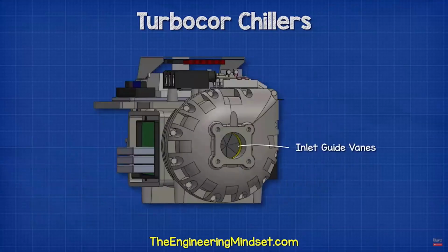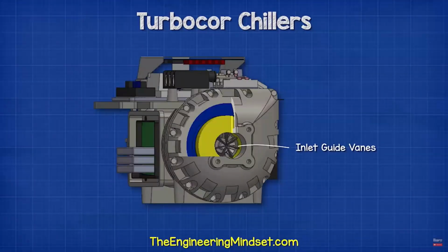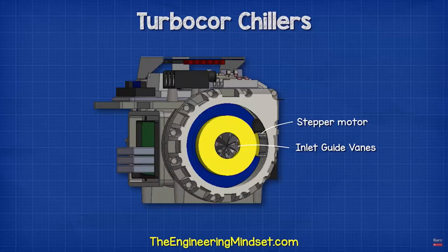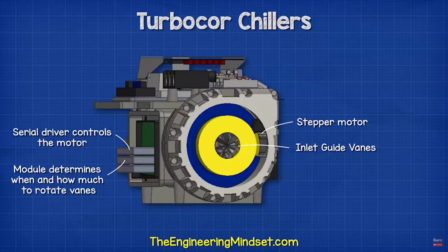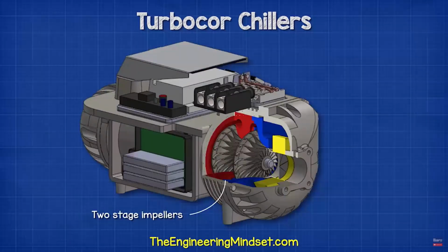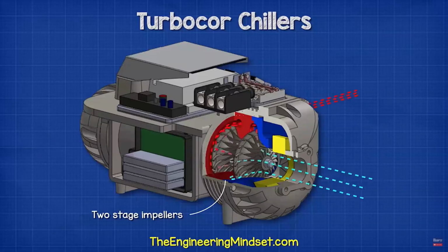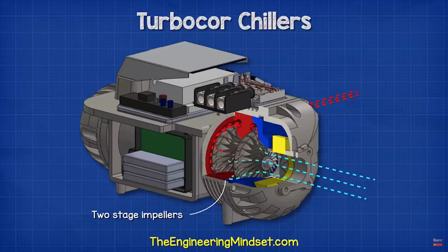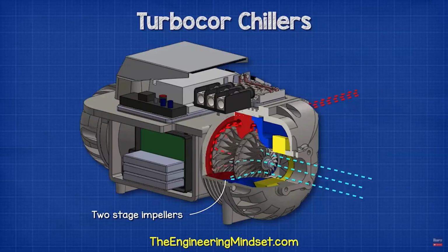For the mechanical parts, we see the inlet guide vanes at the front on the suction inlet. These blades can vary their position and cause the refrigerant to swirl as it enters the compressor impeller. These are driven by an internal stepper motor. The serial driver module controls this motor, and the bearing motor compressor controller determines when and how much to rotate them. These are used during low cooling loads to improve the efficiency and avoid chiller surge, but in normal operation, they are usually left open. Then we have the two-stage impellers. These rotate together. The refrigerant passes through the first impeller and then through a small channel and into the second impeller before entering the volute. From here, it will be ejected from the compressor.